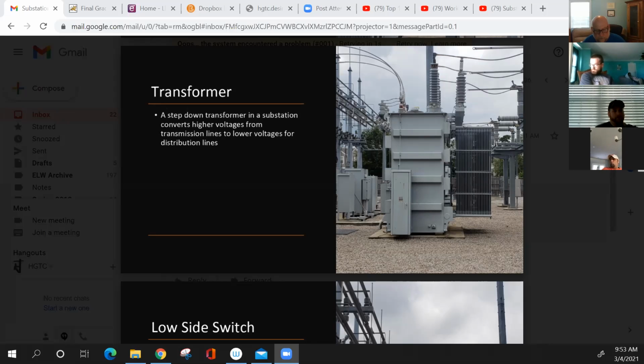Those ranges can be adjusted on the breakers themselves. We also talked about engineering having to adjust tap changers on transformers, or give you permission to do it, because they don't do it themselves. The lineman will do it. They'll give you permission to take care of that.